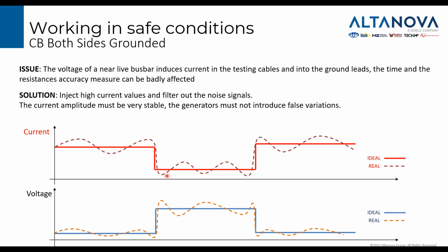First of all, you have a 50 Hertz or 60 Hertz signal in the cables. For example, if you take wires to inject current and the circuit breaker is closed, then you are creating a coil, and all the electromagnetic field that passes through this coil will induce current in the cables, and this must be removed. The same happens for the voltage, of course. The solution is to apply digital filtering, but at the same time, the current amplitude must be very stable. The situation can be even more complicated when you have 2 breaks per phase, because the signal will be even more complicated to analyze.